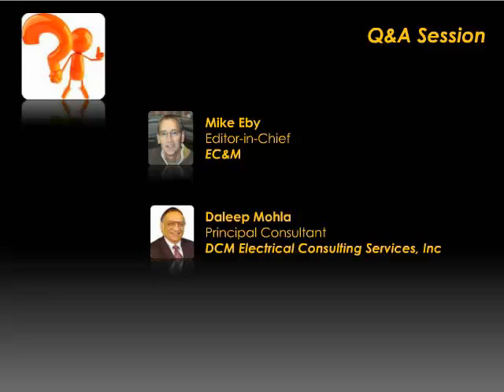Okay, here's a question. You mentioned 3 to 5 cycle opening for breakers. This fast opening is required to limit the arc flash with some of the controls. What is the industry doing to ensure the breakers are in proper working condition to ensure that they actually respond in this type of time frame?